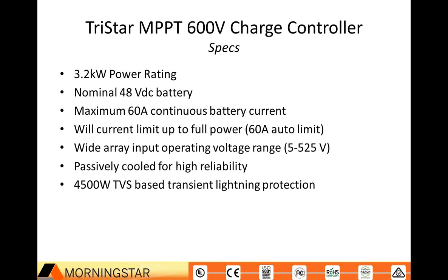So a little bit about the specs of the TriStar MPPT 600 volt. It's a 3.2 kilowatt power rating, and that's the maximum nominal wattage. It's designed to charge a 48 volt DC battery. So unlike the others, it does not work at 12 or 24 volts. It's only for larger systems at 48 volts. Maximum 60 amps continuous battery current, and the device will actually current limit at the 60 amp limit. So if you have a larger array than 3.2 kilowatts, you'll only get 60 amps of output, but it will be able to consistently operate at that level and maintain that throughout the day.